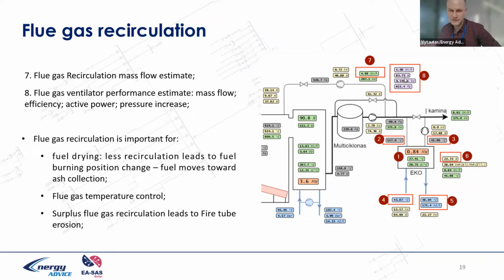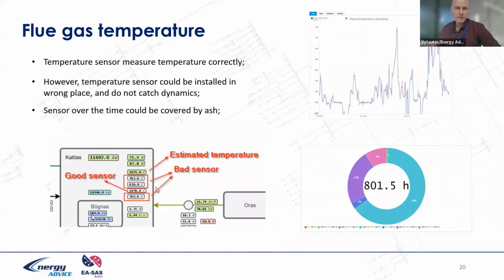So the estimation on the flue gas ventilator allows us to estimate what is happening also in hydrodynamic, computational fluid dynamic terms. What is the pressure distribution inside the furnace? What is the temperature distribution inside the furnace? Flue gas metering. Yes, we also estimate the flue gas temperatures, and here in the furnace we see four temperature sensors, and 3 of them are bad. But our algorithm reacts quite well, the calculated value against the metered value, to the changes inside the furnace.